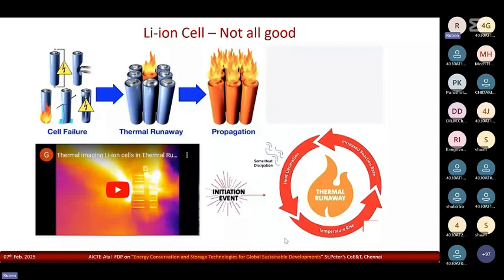Lithium ion batteries are very sensitive to temperature. Their performance is sensitive to temperature, and more importantly, their safety is very sensitive to temperature. You get a better lifespan and safe operation if you operate the battery in the range of 15 to 40 degrees Celsius. Anything lower or higher is a problem. So you must keep these batteries, modules, and battery packs within that temperature range.